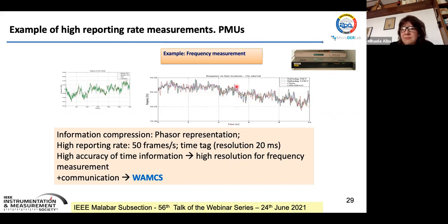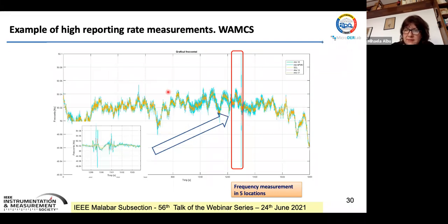Here we have an example of measurements provided by our PMUs located in 4 different nodes, and we can see that frequencies are different. This is not an error, because the measurement has 1 ppm hertz maximal error, so it's extremely precise. This shows that frequency is not a system-wide value; it's not the same everywhere in a defined system, even a large power system. Here we have other examples of such measurements with PMUs, again using high reporting rate.